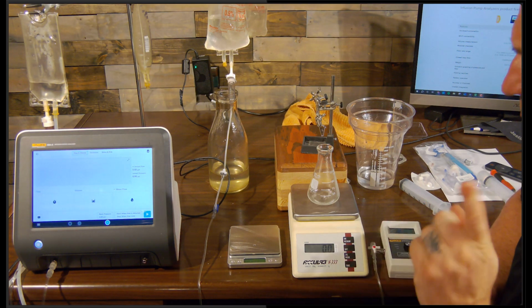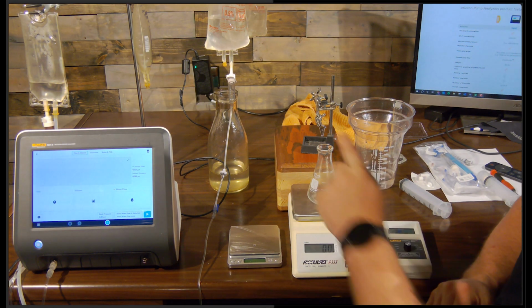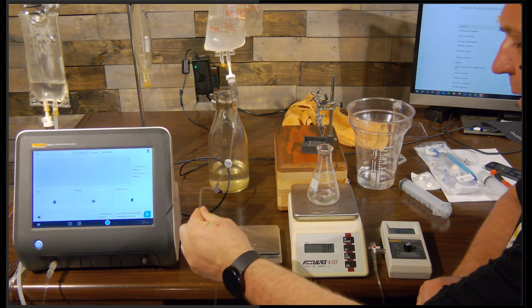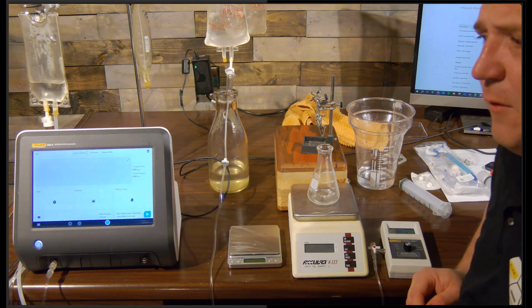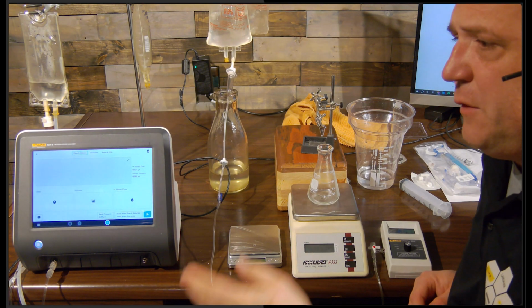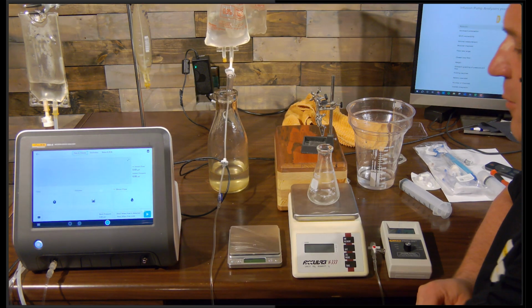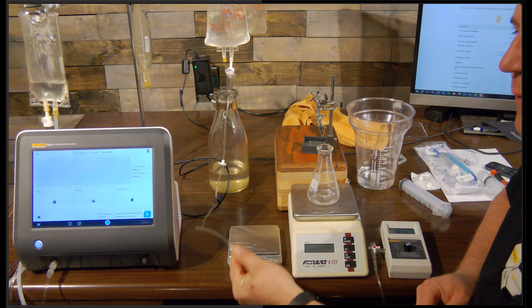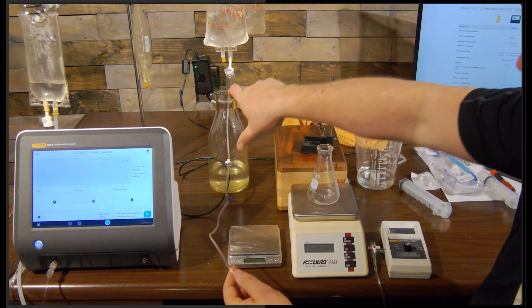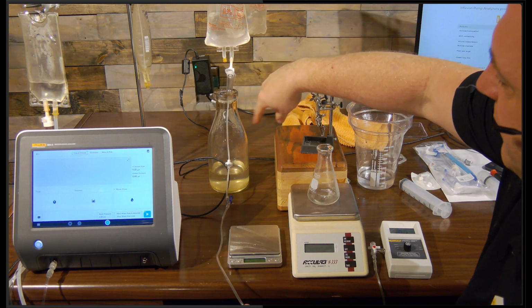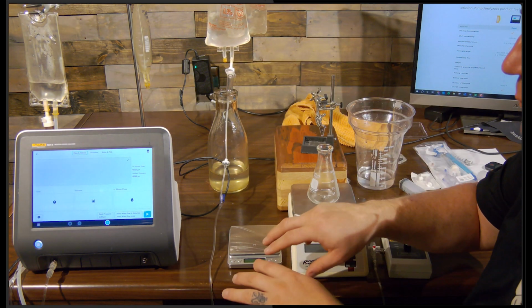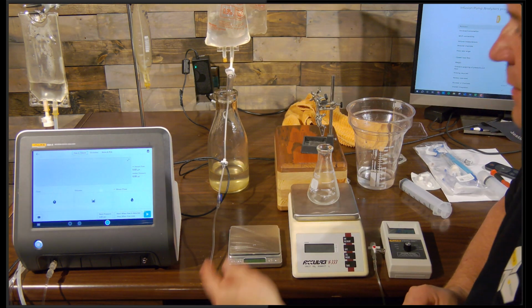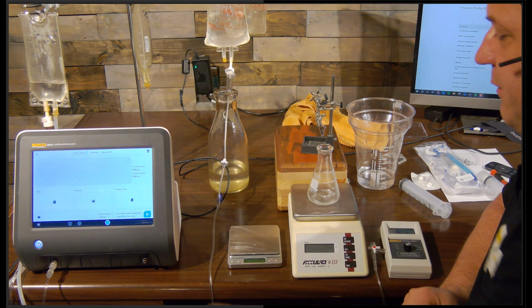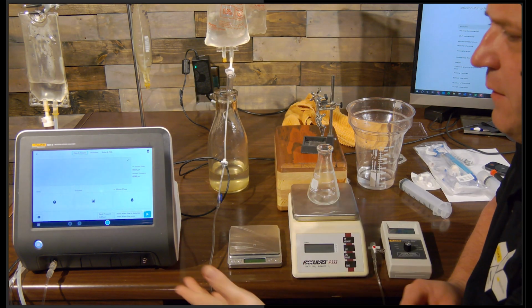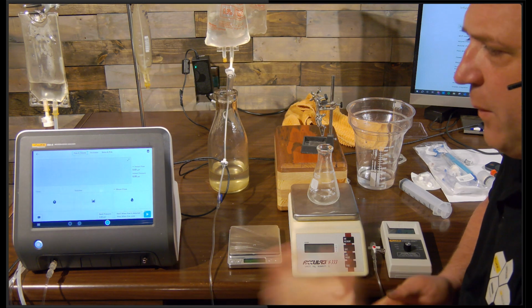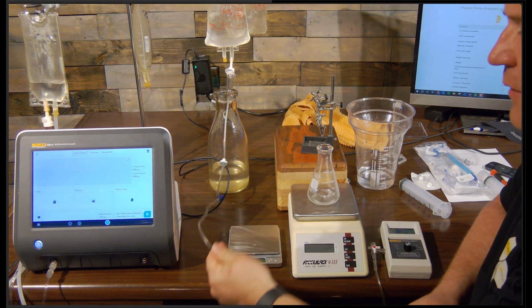And I want to talk about one more thing here with that, and it's this infusion pump tubing. If you read some of the service manuals, they call for you to use 2 sets of tubing. They will have a calibrated tubing set for your flow tests. So it'll have a piece of paper on it with some correction factors, and you'll type that into the software that you're going to calibrate the IV pump with. And then you only use this for flow tests, and you can only use it for so many tests. I don't remember what it is, 20 or so tests, and then you're supposed to change out this tubing.